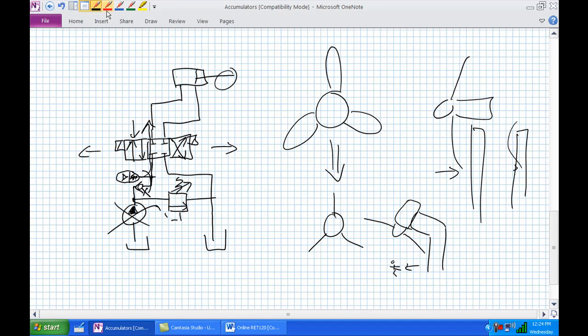You go ahead and shut off the pump and you move it to a safe location. You're removing all sources of stored energy, so you've locked out and tagged those things out. What is another source of stored energy? Quite obviously the accumulator. The accumulator is charged up to an incredible pressure, has a certain volume in there that will actually perform work, and that work may be crushing you.